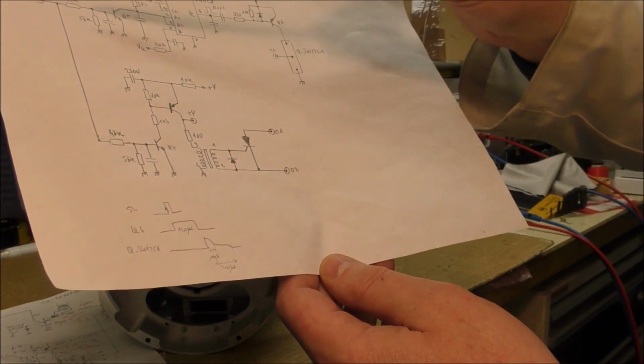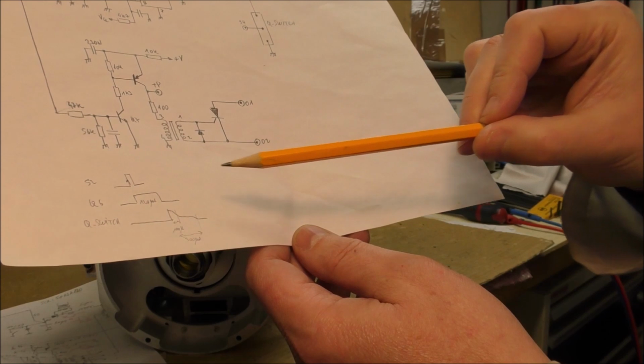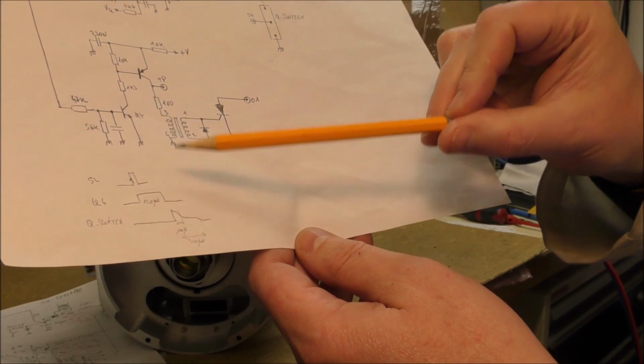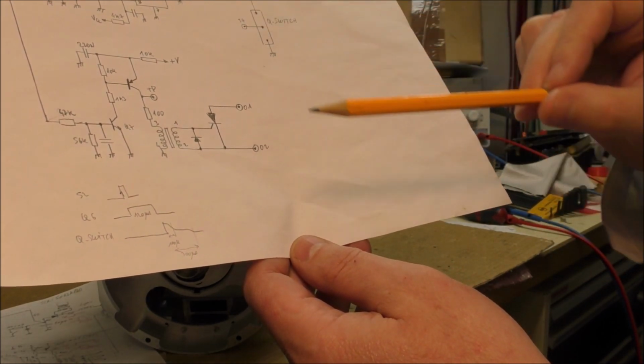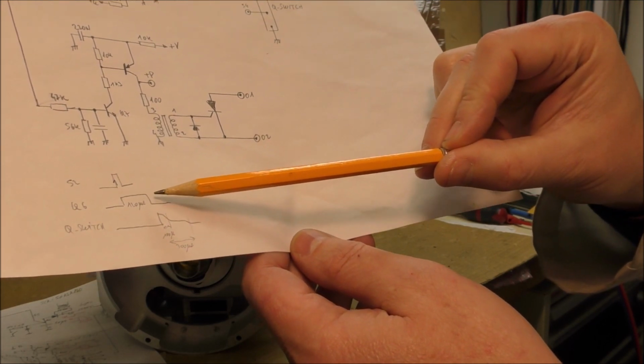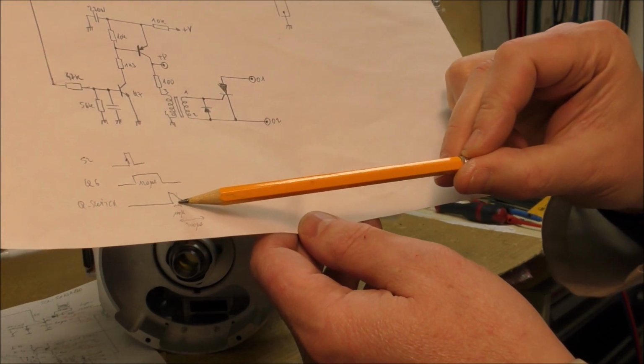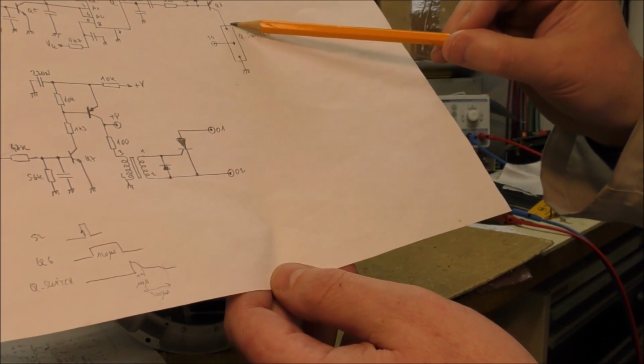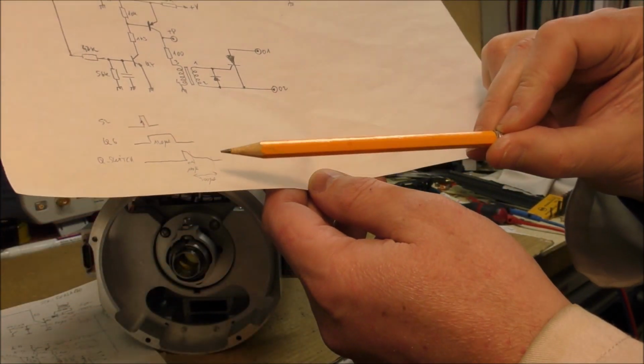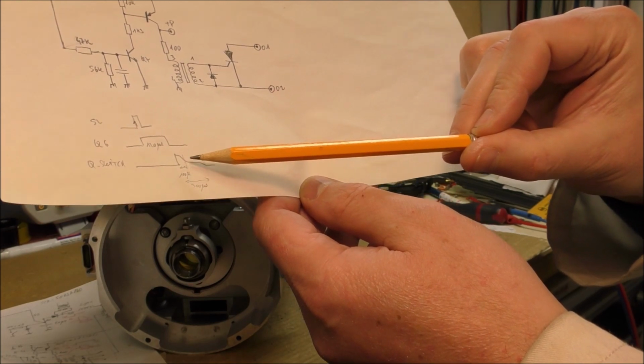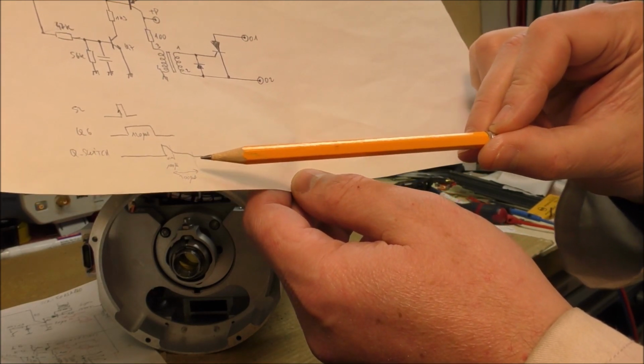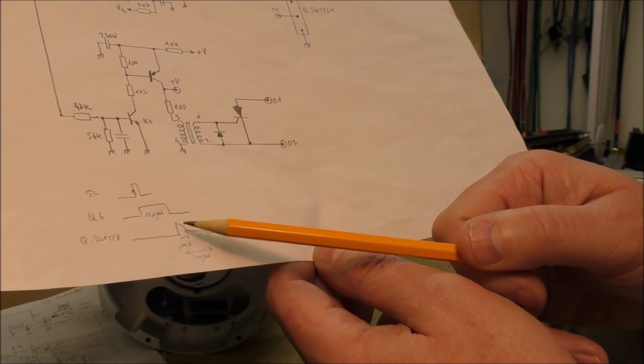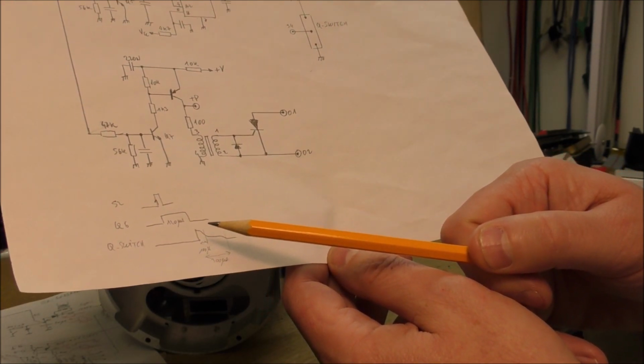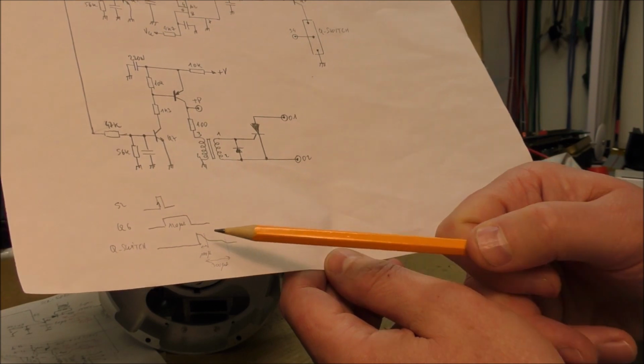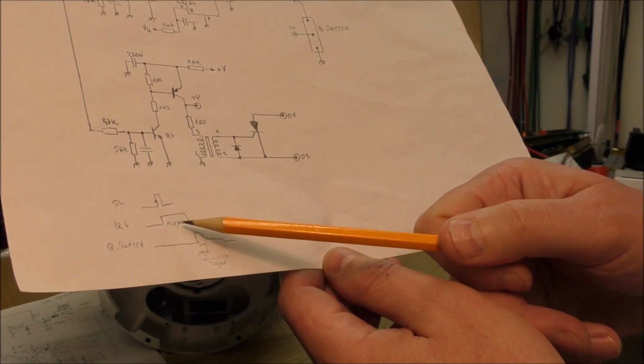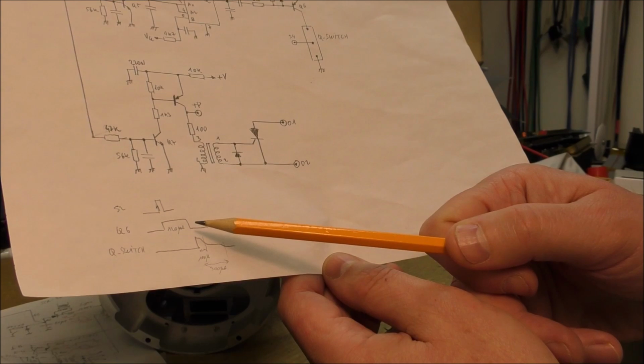This is the input pulse, this signal here. This is the output of the monostable, pin 6 here. The duration is 120 microseconds. And this is the signal at the input of the transformer for the Q switch. So the duration of the pulse is around 100 microseconds also. At this time, the feedback of the laser is activated, so the laser beam is generated. This time is important, it permits to have the optimum pumping of the ND-YAG crystal rod.